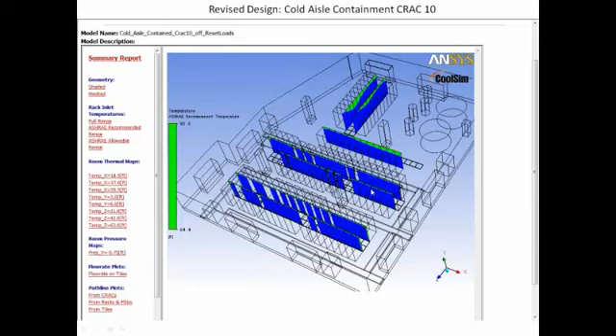Well, absolutely. If you don't do it right, just remember that when you do a containment, it generally means that the cold aisle, in this case, is going to be cold, but that also means that the hot aisle or the hot aisles, they're going to be hotter. Yes. So if you have any openings now, unintentional openings between the cold aisle and the hot aisle, and you get recirculation, it can actually be a worse situation than you had before.